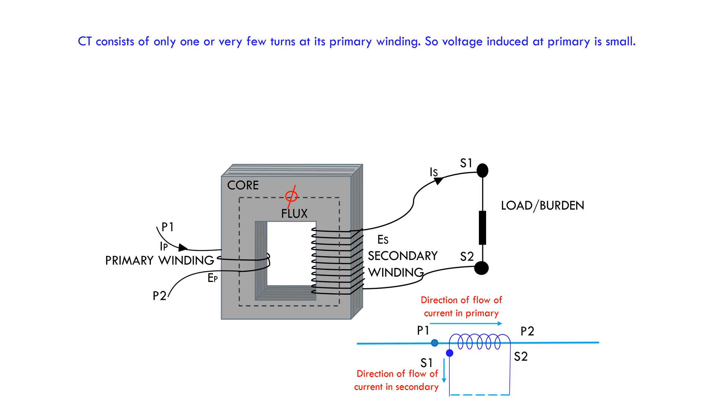The CTR, CT ratio 600 by 1 ampere means when primary current is 600 ampere then secondary current will be 1 ampere. Current in secondary winding will be increased or decreased proportionally with the increase or decrease of primary current. The same formula is applied here as power transformer.